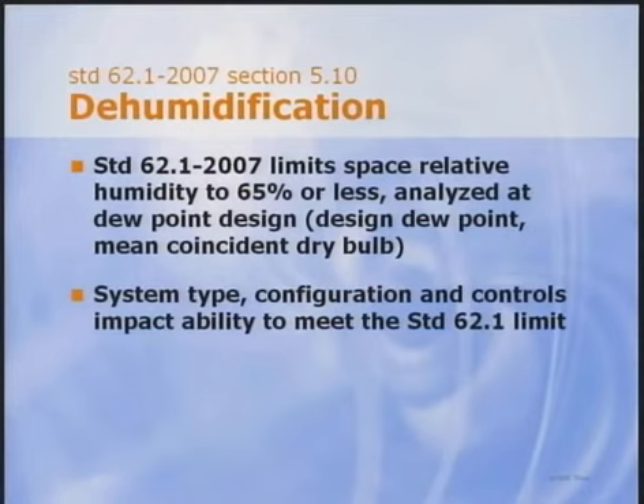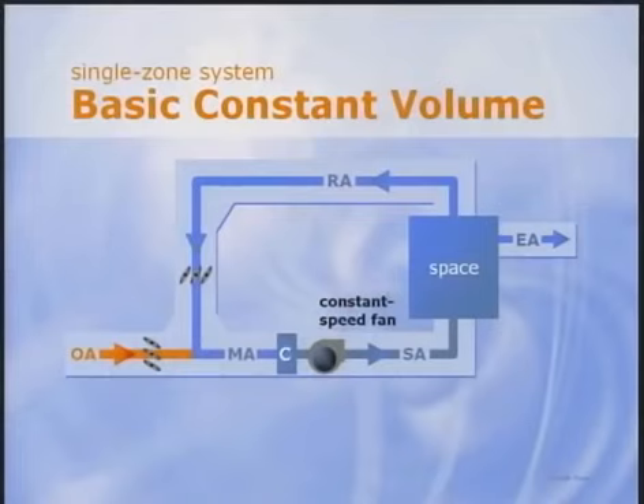This analysis evaluates the dehumidification capability of the proposed HVAC system at one particular load condition. Depending upon building design and climate conditions, some systems can meet this requirement without direct humidity control. Other systems can't. Let's look at a few systems analyzed as required by Standard 62. Perhaps most common, the single-zone constant volume system supplies a constant quantity of mixed air to a single zone at a temperature that depends on sensible load.